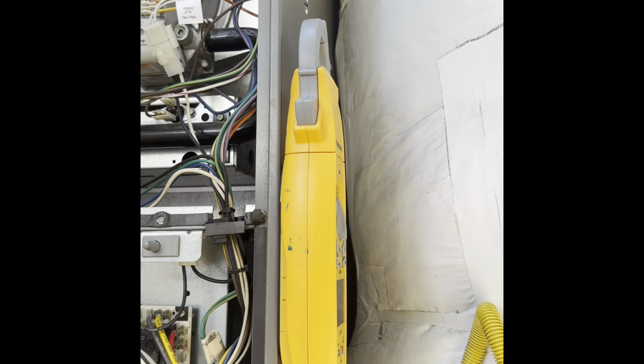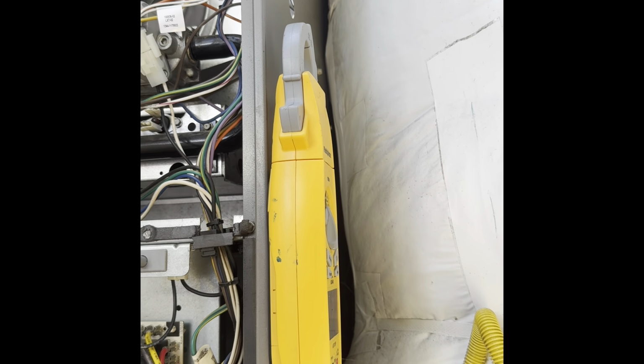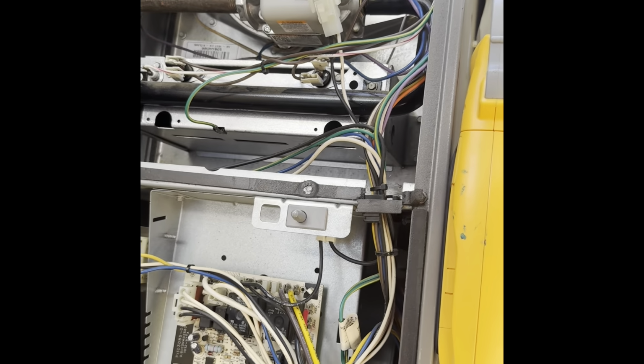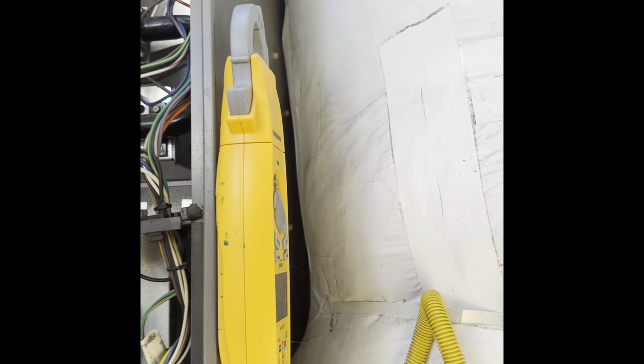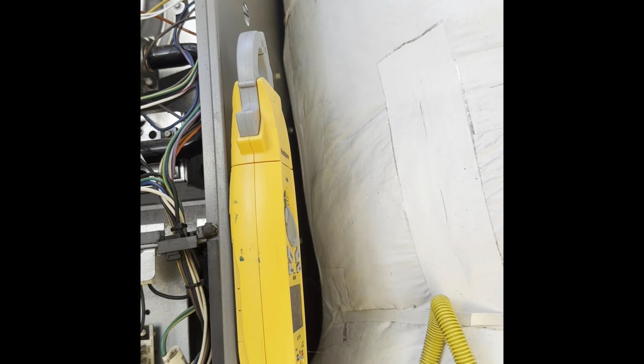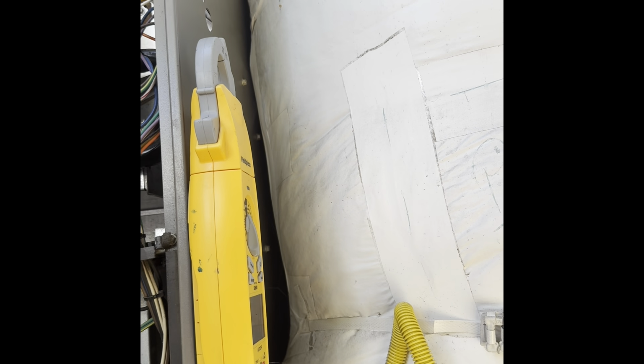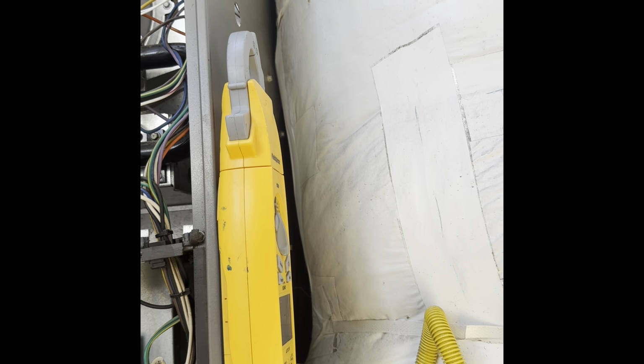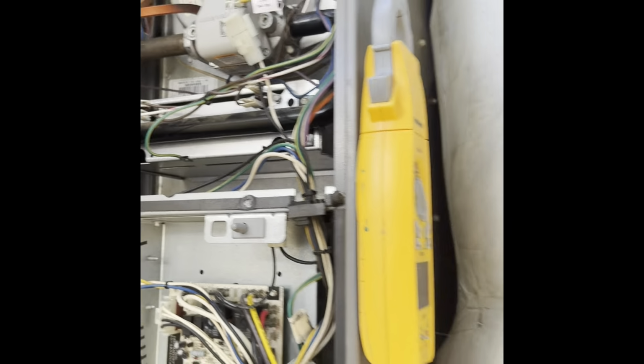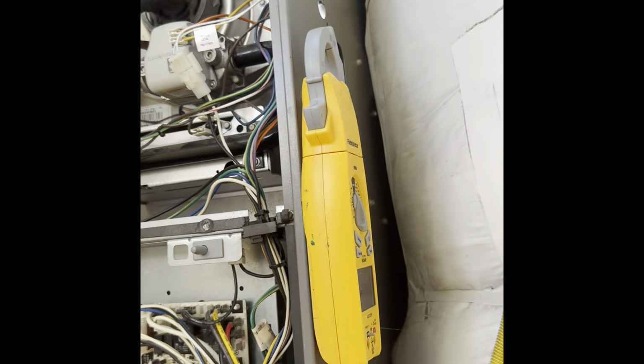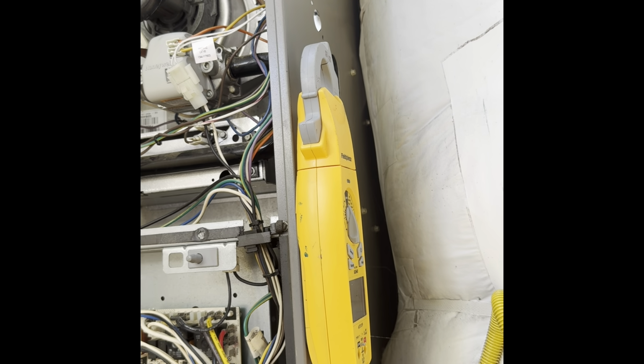Okay, so we already checked the board. We already checked the flame sensor. We already checked the igniter. We checked amp ratings for the inducer. I still haven't checked the amp rating for the blower itself. We still have to check the temperature split to see what the temperature is right now. We put the temperature between what's going inside the unit and what's coming outside the unit. That's what we call a temperature split, or temperature rise in heating.